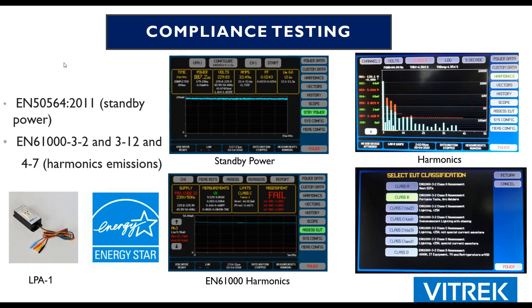The bottom left screen, an actual screenshot from our unit, enables you to assess a piece of equipment under test and run that test for the specified period of time. Similar to the standby power test, this gives you the acceptable levels for harmonics.